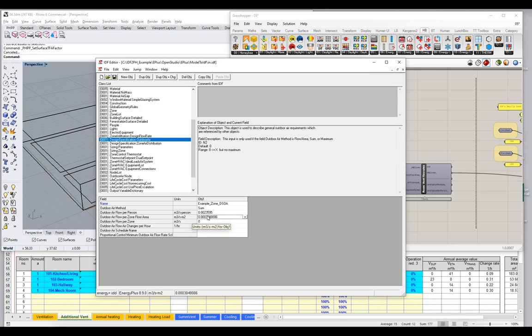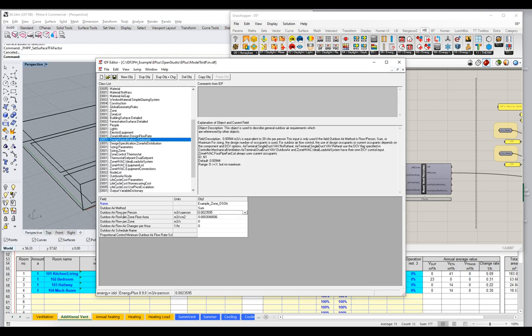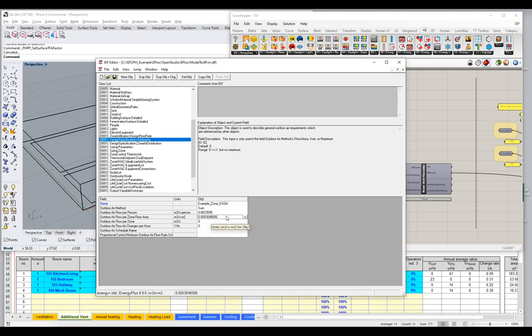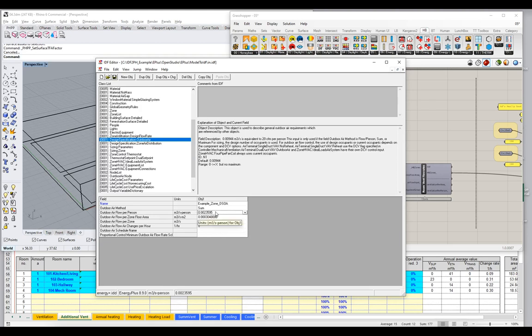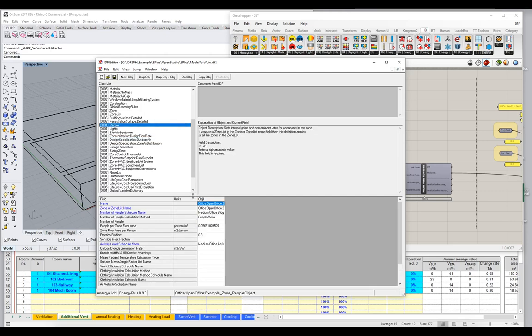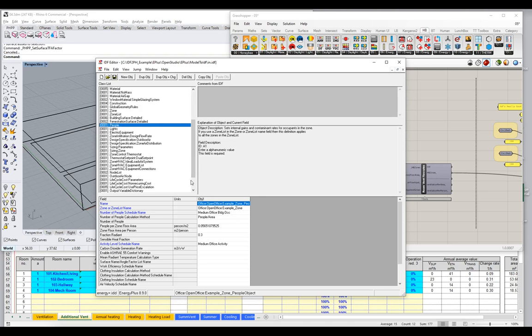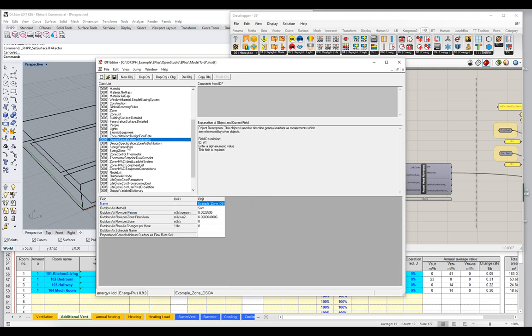And then we have the option to put in some other air flows. Those are zeroed out. So the way that the Honeybee works by default is going to apply an airflow per person and then an airflow per square meter of floor area. And remember, if we want to figure out how many people there are in the space, we would have to figure out what our occupancy load is. And then we would have to go find the schedule that describes what is the percentage of maximum number of people in the space, which is going to go up and down over the course of the day and the week.